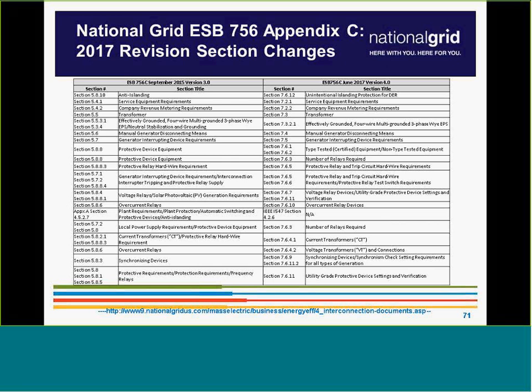So, 7.6.12 is unintentional islanding. You'll definitely want to look at section 7.3 for effective grounding and your transformers. Section 7.4 is your manual generator disconnect. 7.5 is your interrupting device requirements. And my favorite, all of section 7.6, is all of your relaying and the associated equipment with that.